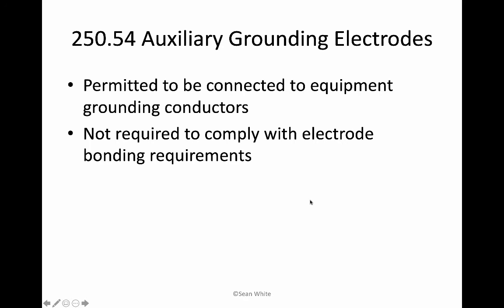And it was required to do that in the 2014 National Electrical Code, but then they made it less required because people were boxing over it at the NEC meetings. And it's also not required to comply with electrode bonding requirements. And so that's this weird auxiliary grounding electrode.